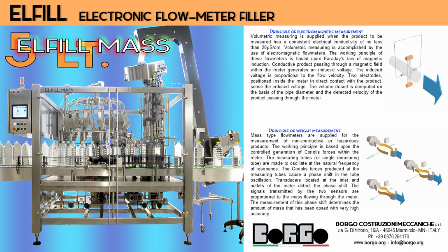Mass-type flowmeters are supplied for the measurement of non-conductive or hazardous products. The working principle is based upon the controlled generation of Coriolis forces within the meter. The measuring tubes, or single measuring tube, are made to oscillate at the natural frequency of resonance. The Coriolis forces, produced at the measuring tubes, cause a phase shift in the tube oscillation. Transducers, located at the inlet and outlet of the meter, detect the phase shift. The signals transmitted by the two sensors are proportional to the mass flowing through the meter. The measurement of this phase shift determines the amount of mass that has been dosed, with very high accuracy.